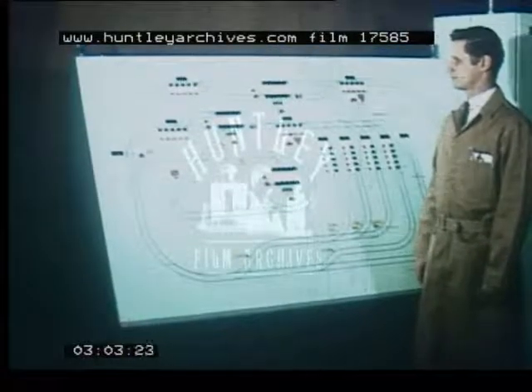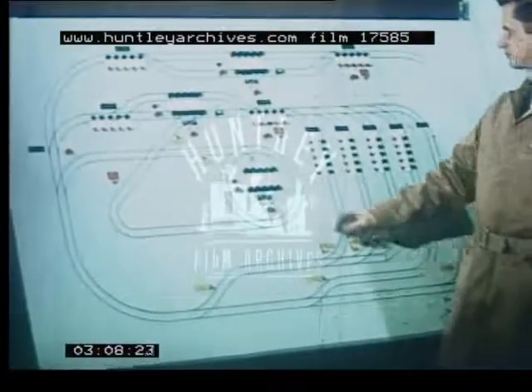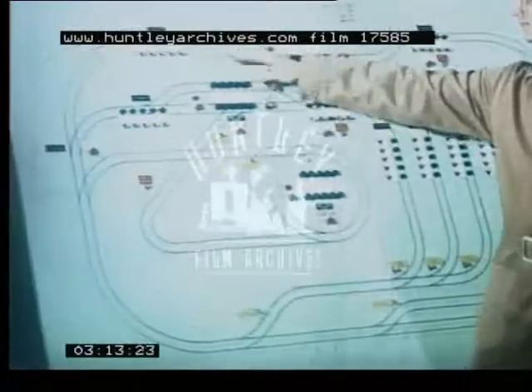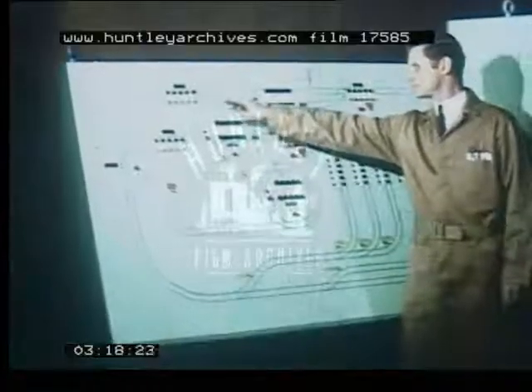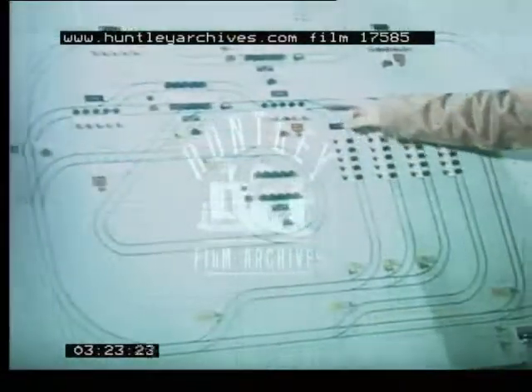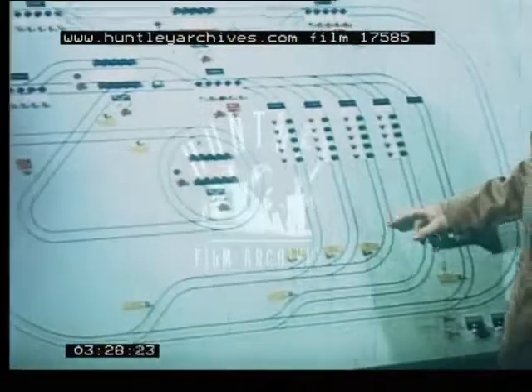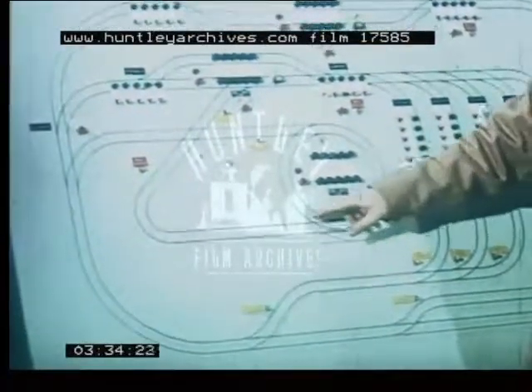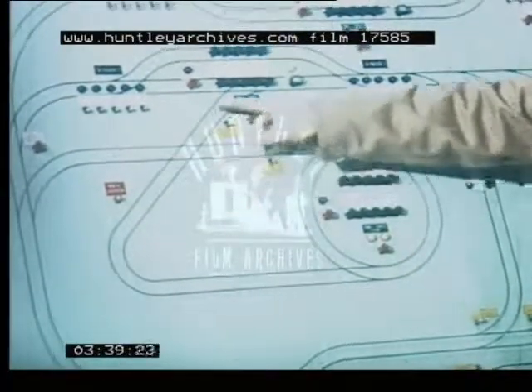The prototype system, as shown on the schematic control board, is laid out as follows: two concentric loops — one representing the interline system track, and the other an airline in-terminal loop system. There are two sidetrack stations, one on each loop, both capable of diverting baggage and inserting it into the system. There are four shunts along the inner loop section. The first three represent horizontal hold areas; a fourth shunt demonstrates a 90-degree vehicle climb and descent. An elevated circular storage area off the main line demonstrates the direct call baggage claim feature.